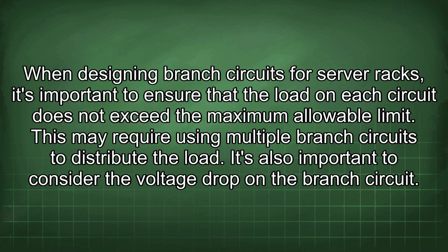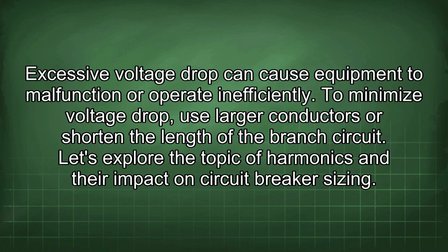When designing branch circuits for server racks, it's important to ensure that the load on each circuit does not exceed the maximum allowable limit. This may require using multiple branch circuits to distribute the load. It's also important to consider the voltage drop on the branch circuit. Excessive voltage drop can cause equipment to malfunction or operate inefficiently. To minimize voltage drop, use larger conductors or shorten the length of the branch circuit.